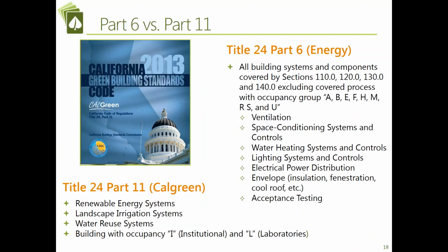So Part 11 used to house commissioning. That used to be its home before this 2013 code cycle. In the 2013 code cycle, the energy aspects of commissioning moved over to Title 24 Part 6, because that's the chapter of the building code of Title 24 that it really belongs. But some aspects of commissioning stayed behind in Part 11 because they didn't apply to those features of the building that Part 6 applies to. So Part 11, our CalGreen code, still has commissioning requirements for the renewable energy resources of a building. Part 6 is all about what's built into the efficiency of the building, not what is the generation of energy. So Part 11 still deals with that renewable energy generation systems of the building.